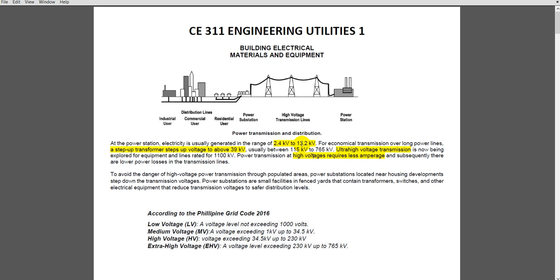So these are the types, the classification of voltage. We have low voltage, level not exceeding 1,000 volts; medium voltage, 1 kilovolt up to 34.5 kilovolts; high voltage, exceeding 34.5 kilovolts to 230 kilovolts; and extra high voltage, 230 kilovolts up to 765 kilovolts. So this is the simplified way of how power is transmitted to our homes. So, next, let's go to the service entrance.